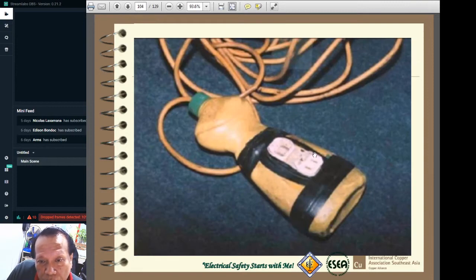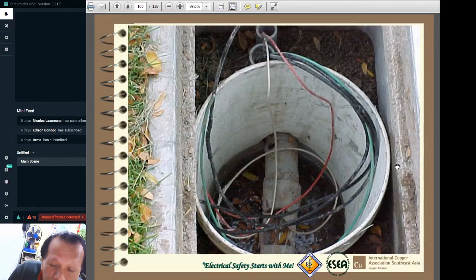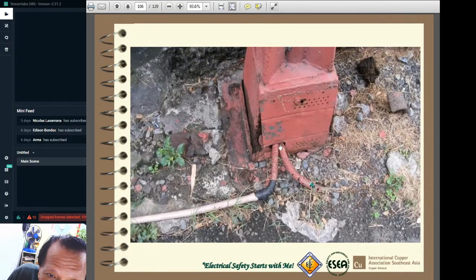And again, this kind of temporary portable outlet should be avoided. It's a more professional, safer way of providing for an extension cord. And similar with this, the installer just simply provided a temporary manhole or pole box, which is improper. And so with this, you would see these conduits almost being damaged because this flexible conduit is not a standard thing to use outdoors, like in this case.